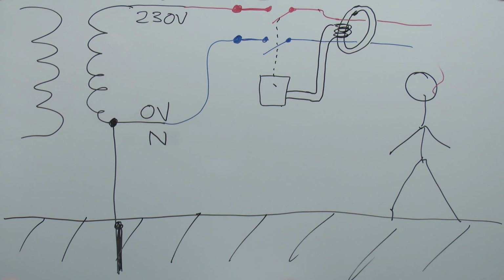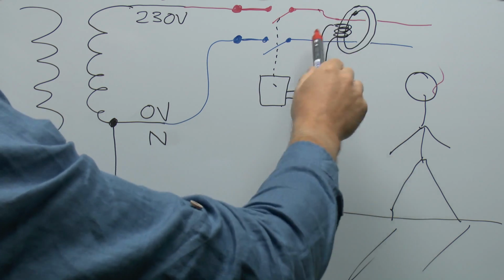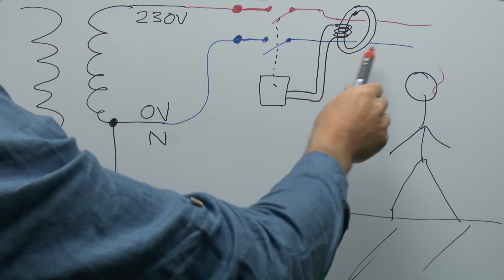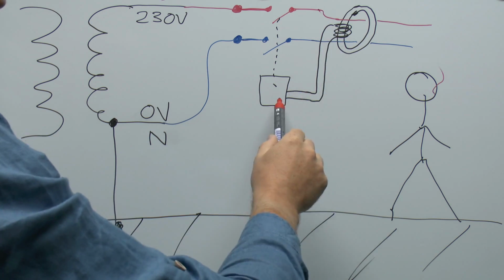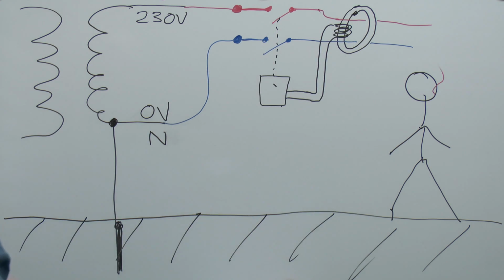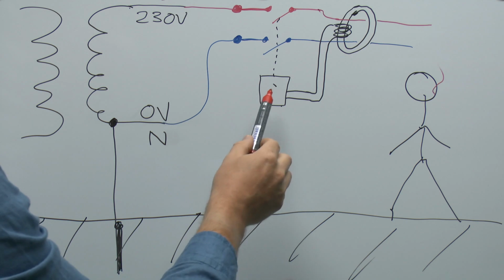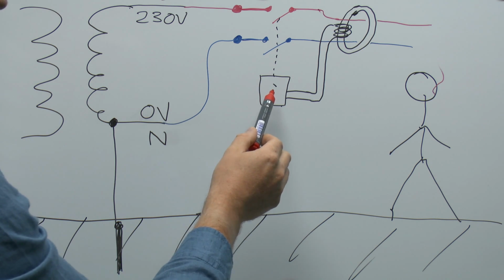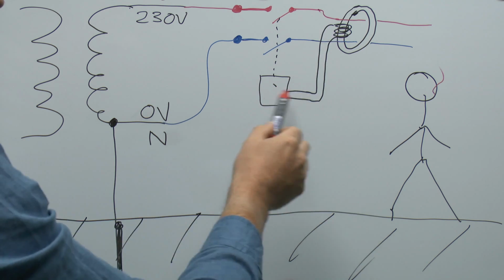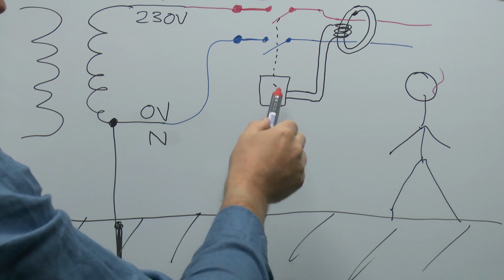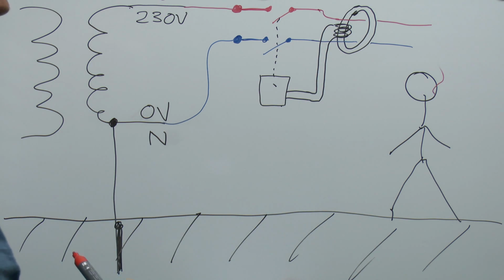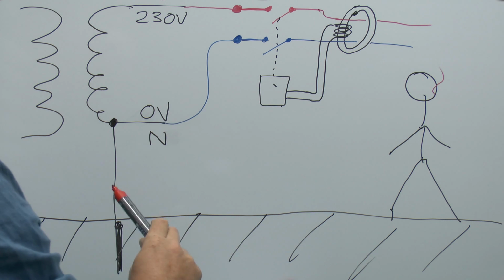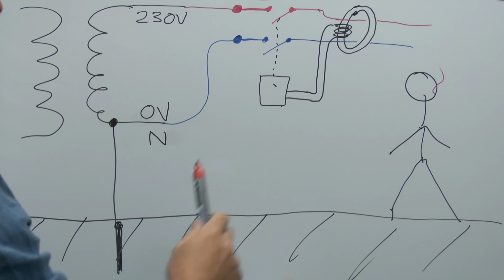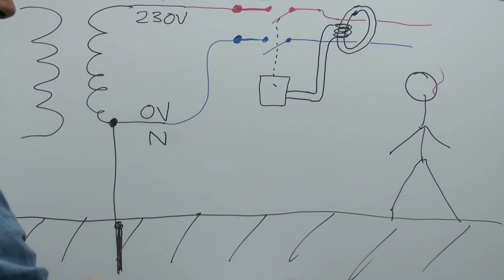And in this scenario, of course, the wires going through can be any size you like. They're just going literally straight through the centre, and again the sensor coil just detects the current imbalance and will trip the device as necessary. This is generally how the modern RCDs are actually created, and the sensing device here could be, in theory, just a solenoid with an appropriately arranged coil here and a coil here. But again, in modern ones, it's generally some kind of electronics in here, which contains an amplifier and various other things to obviously trip it at the predefined leakage current.